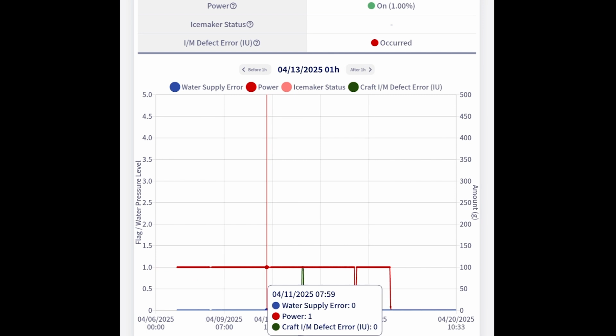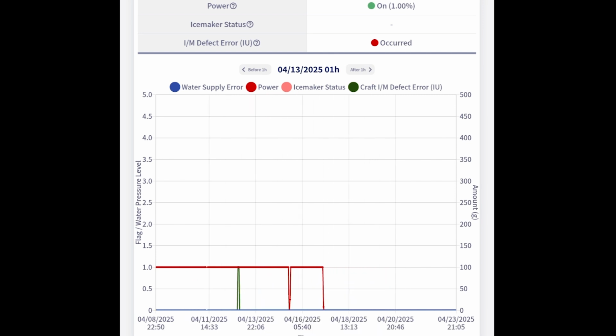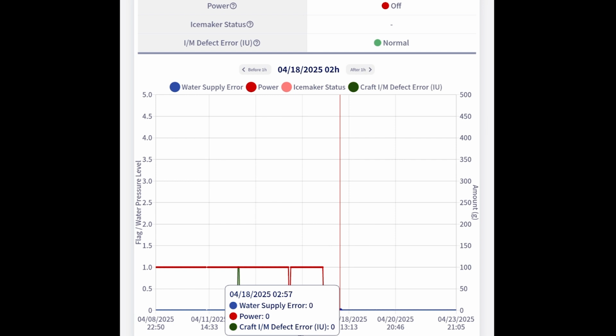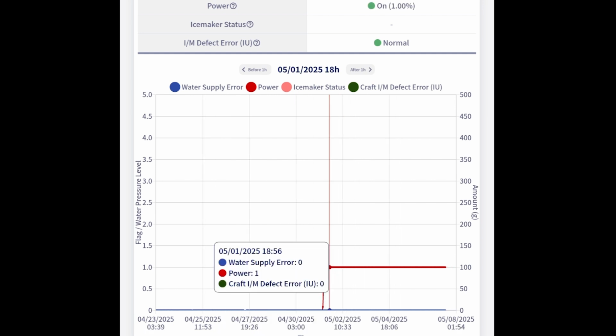And then shortly after that, if you notice, your red line drops down, and that's where the customer powered the ice maker off. So look, your power is now at 0. So in that time frame where it was powered off, the ice maker was likely replaced. And then right here around 5/1, we see that the ice maker was powered back on, and it's been working okay since because there's no more errors. So that's how an IU error code will display.